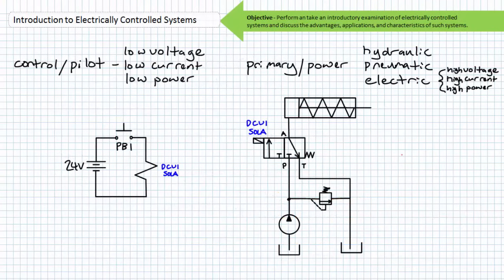One of the most fundamental characteristics of an electrically controlled system is the differentiation between the control signals and what is being controlled. The control signals are typically low voltage, low current, low power signals and are entirely separate and electrically isolated from that aspect being controlled, whether it is hydraulic, pneumatic, or high voltage, high current, high power electricity. The control signal is often called a pilot signal. The power input is often called primary input, and you'll hear me use these terms interchangeably.